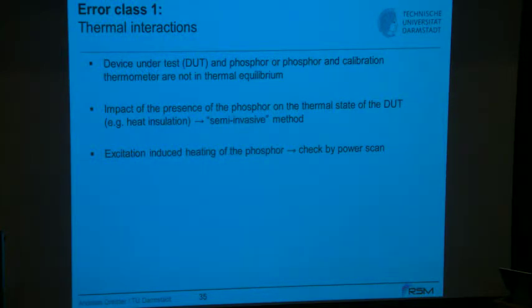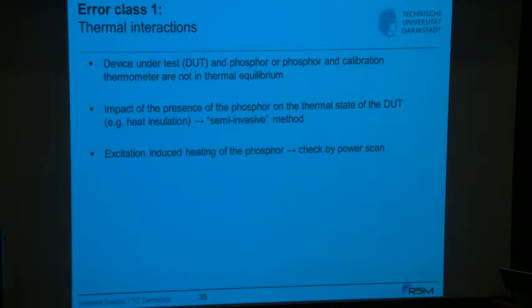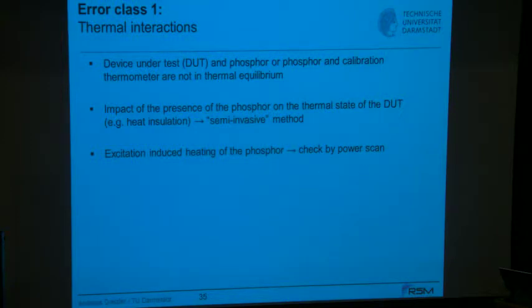There is another impact: you may heat the phosphor with the laser pulse. You shoot perhaps a millijoule onto a certain area and part of that energy will be absorbed. Most of the absorbed energy causes the electronic excitation from which phosphorescence takes place, but a larger part heats up the phosphor itself. This should be assessed in a power scan, and in the high-speed thermometry application example I will show the impact — it can easily be a couple of Kelvin.